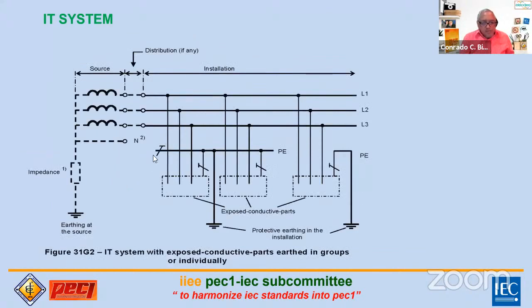So in the IT system, we have what we call a group. In the installation, the exposed conductive parts are connected as a group. Or individually, you can have earthing in its equipment, okay, isolated, but still part of the system. So what are the requirements? What happens when you have a ground fault? Because in an IT system, we don't want to open the overcurrent protective device during the first fault condition.